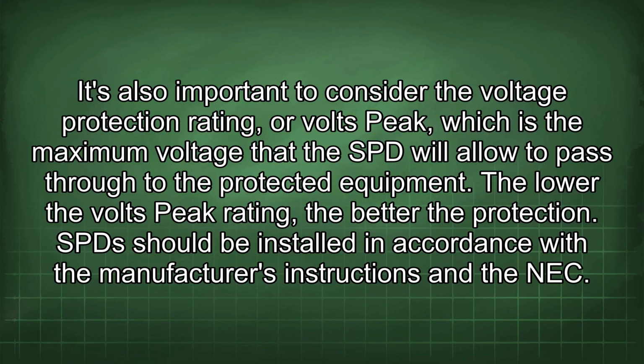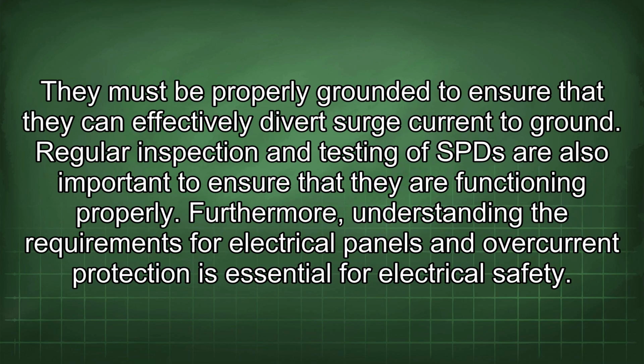The lower the volts peak rating, the better the protection. SPDs should be installed in accordance with the manufacturer's instructions and the NEC. They must be properly grounded to ensure that they can effectively divert surge current to ground. Regular inspection and testing of SPDs are also important to ensure that they are functioning properly.